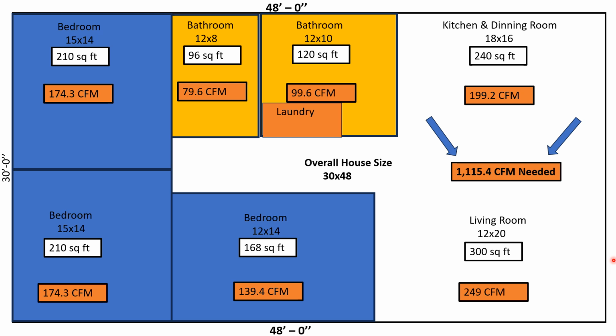So here's how we're going to do it. We take the 3 ton, 1200, divided by 1440, which is our square footage, and get our 0.83. Then we take the square footage of each room and multiply that by 0.83. That tells me how many CFMs each room needs, and I have a total of 1115.4. That's the minimum I have to set my capacity at. And you're asking me, what do you mean when you say set the capacity?